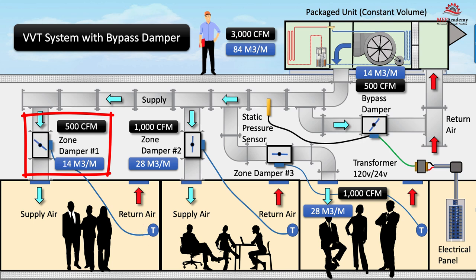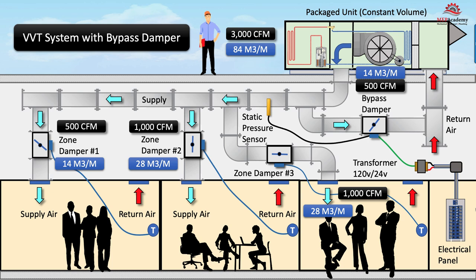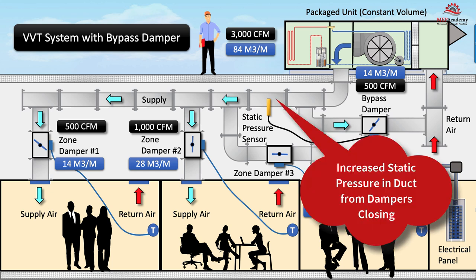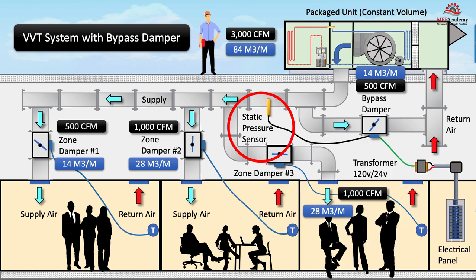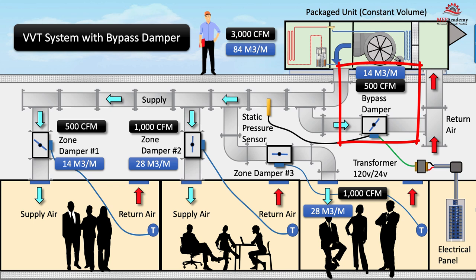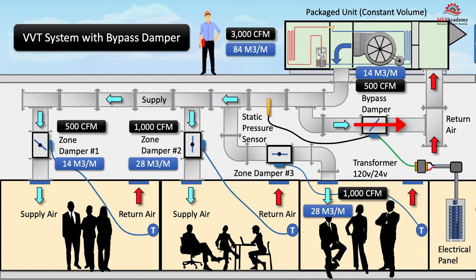If the controller for zone damper number one requires less air and the damper modulates down to deliver only 500 CFM (14 cubic meters per minute), then only 2500 CFM (70 cubic meters per minute) of the total air is needed by the zones. As zone damper number one modulates to partially closed, the pressure in the supply duct increases. The static pressure sensor sends a signal to the bypass damper controller to modulate open, allowing the excess 500 CFM to pass from the supply air to the return air duct without entering any of the zones.